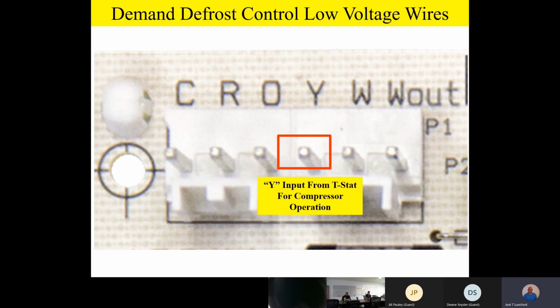The Y terminal is the input from the thermostat for compressor operation. Now, it should be noted, it doesn't matter if it's heating or cooling mode, that compressor is going to be running. The only difference is that in the heating mode of operation, the O terminal will not be energized, but we'll still have the Y input because we're still going to have that compressor running on the heat pump in the heating mode of operation. So Y is our input from the thermostat for compressor operation for both heating and cooling mode.